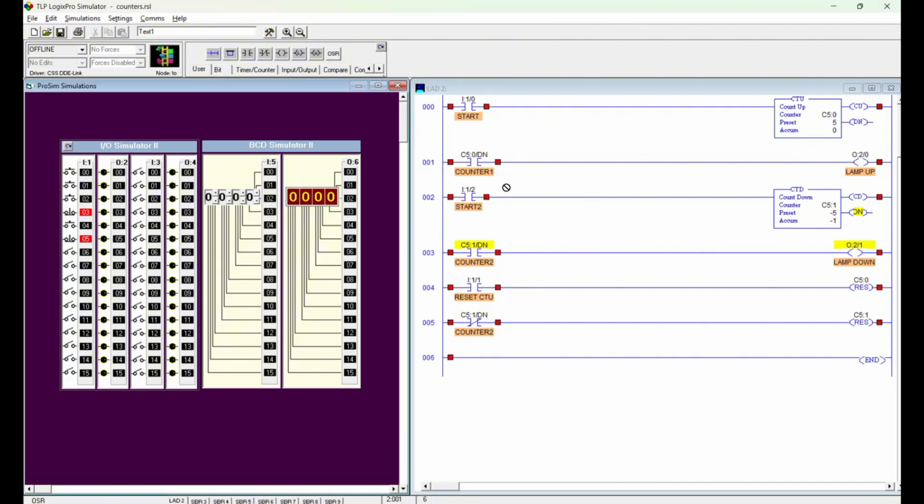I will drag that in here, my marker address. So I will put an address like B3:0/1. That can be my address for this OSR. And as an output, it produces a single pulse output for one program scan when the transition input goes from off to on. So we will do a reliable auto reset using this without any unwanted increments.